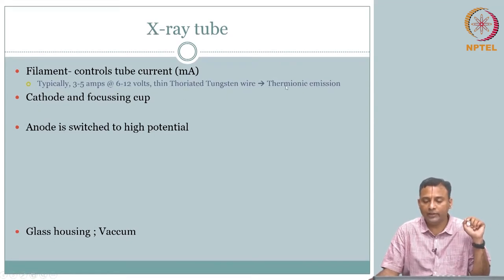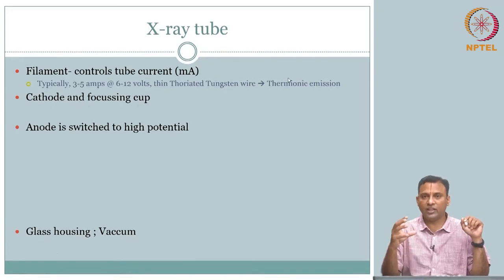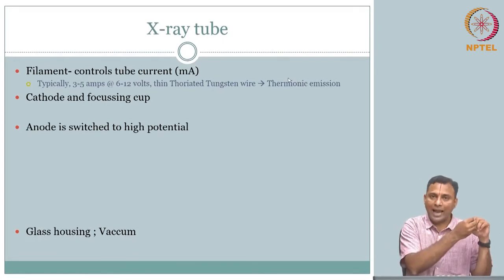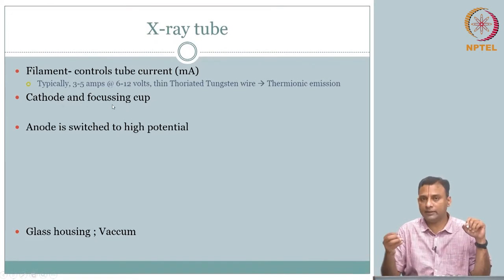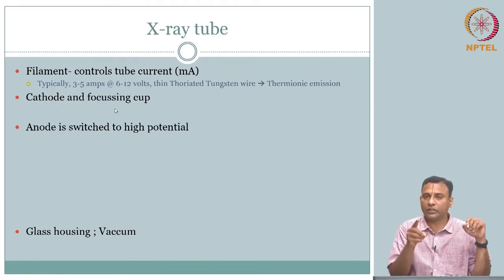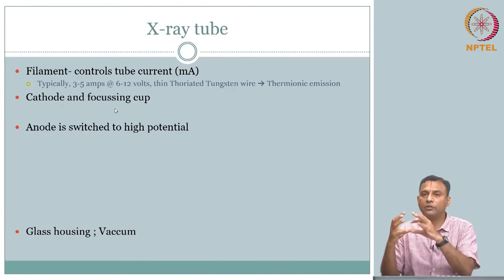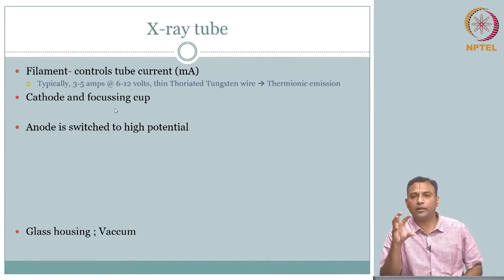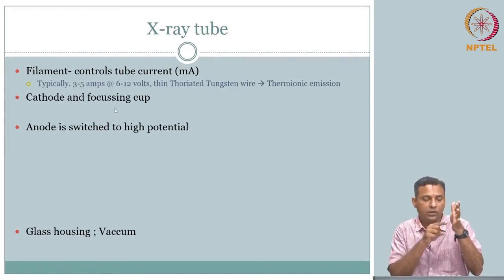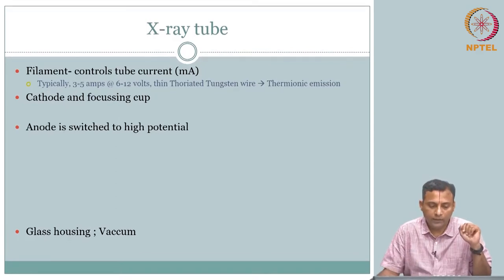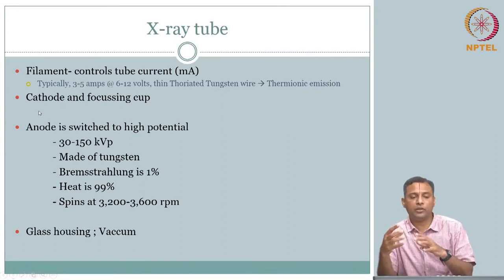Using thermionic emission you get the free electrons. By varying the filament circuit you can have the electrons ready — free electrons on the cathode side are created. Then you have the focusing cup, which directs all the electron cloud in the direction you want, straight into the anode surface where you want to hit it. At this point we say the x-ray tube is primed — electrons are ready.